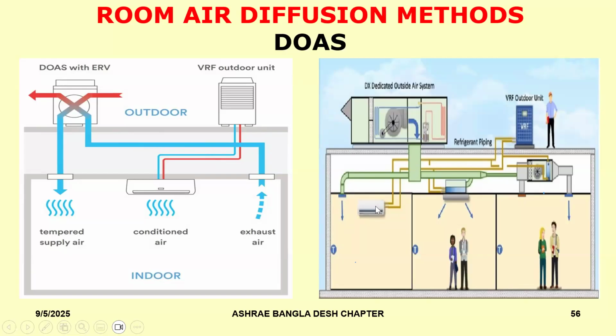Typically, for example, you can also visualize a hotel room where you have a fan coil unit, and you have a separate unit which brings in the treated air. Here, this treated air can be mixed along with this air or here. So the return comes here, mixes with the outside air, and that comes into the space. So this is what we call a dedicated outdoor air system.